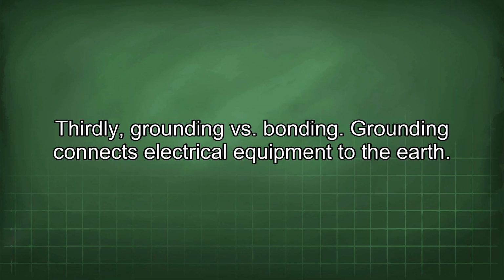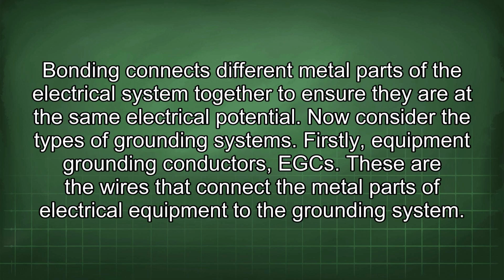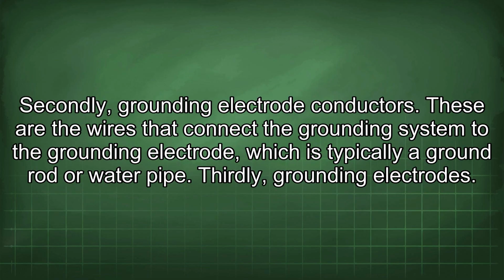Thirdly, grounding vs. bonding. Grounding connects electrical equipment to the earth. Bonding connects different metal parts of the electrical system together to ensure they are at the same electrical potential. Now consider the types of grounding systems. Firstly, equipment grounding conductors, EGCs. These are the wires that connect the metal parts of electrical equipment to the grounding system. Secondly, grounding electrode conductors. These are the wires that connect the grounding system to the grounding electrode, which is typically a ground rod or water pipe.